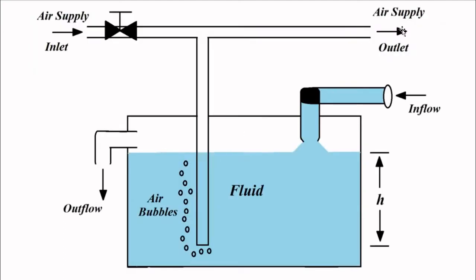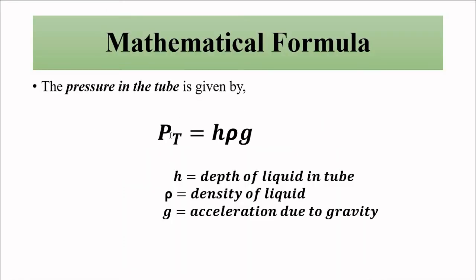Once we get the pressure, this output supply pressure, then we can connect any other pressure measurement device. It can be bellows, it can be diaphragms, it can be Bourdon tube pressure gauge, or any other force measurement device. We can get a direct readout in terms of density because the pressure which we calculate, we simply divide it with the product of h and g, and that will give us density rho. Because g and h are fixed, the output can be directly calibrated in terms of density.